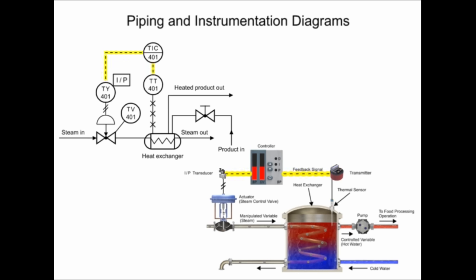A dashed line between components indicates an electrical signal. The controller and indicator is the instrument where the transmitter sends an electrical signal and is shown in the functional identifier at the second and third letters, I and C. Balloons with a solid dividing line indicate that the instrument is board mounted.